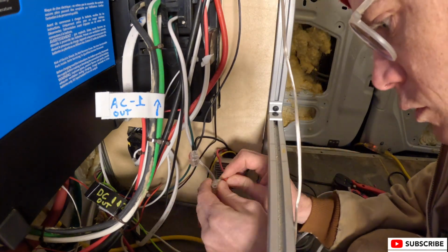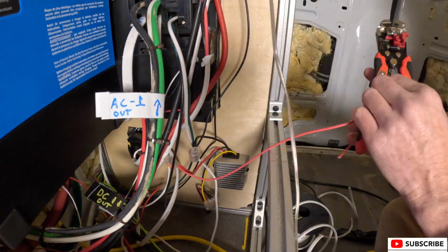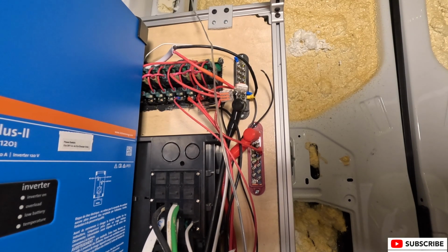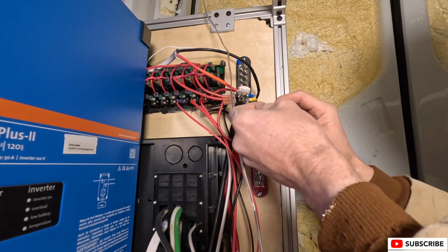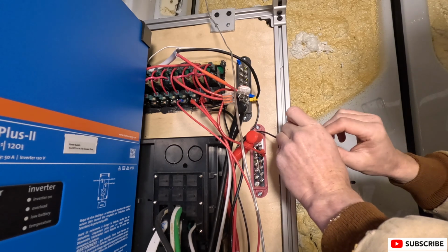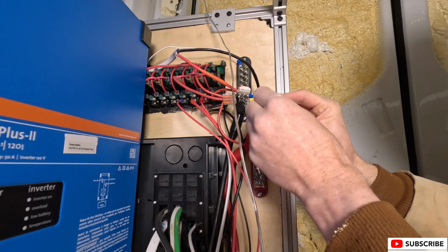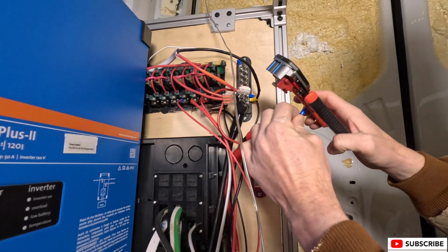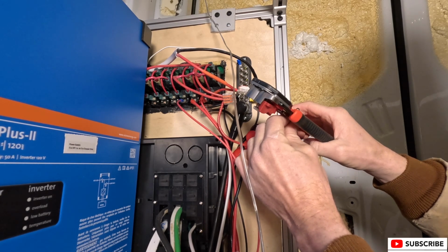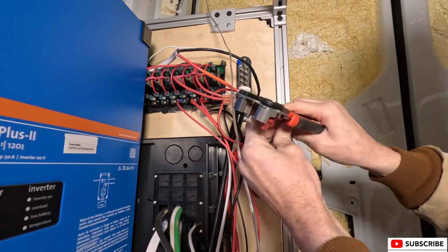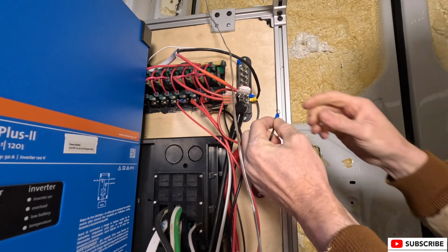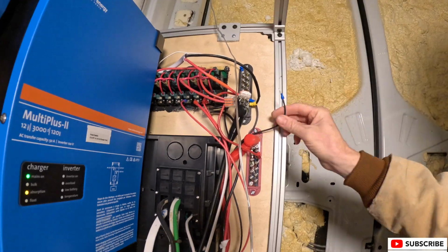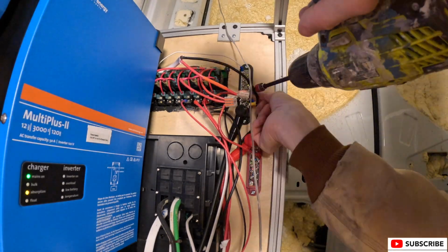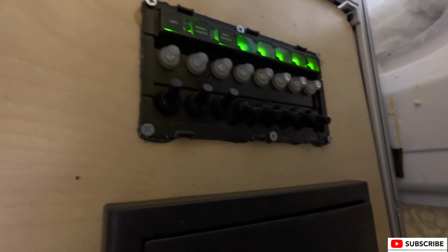All right, so now we're connecting to the 12 volt system, which ground is the black wire, and that's just going to common ground, which is our black bus bar. And then red is going to this toggle switch here, which is the fourth one over in the top toggle switch assembly. So right now I'm finishing up the ground, and I have the positive already connected, and you can see four red wires connected on the right side of the back side of the toggle switch assembly. The one on the farthest left with the blue coupling is what's going to the Starlink, and that's powered from the DC bus bar with 2 6 AWG gauge power cords.